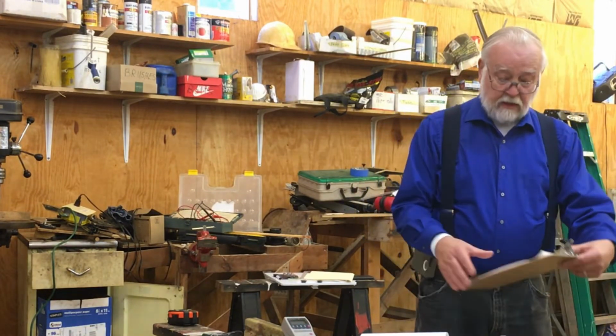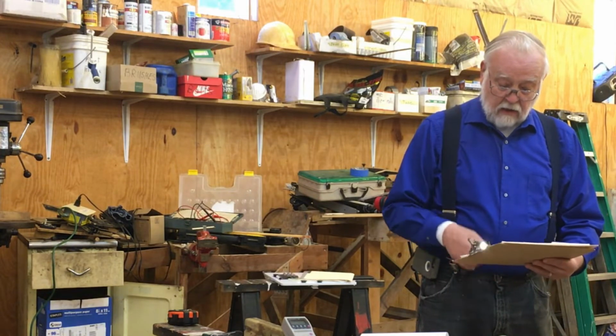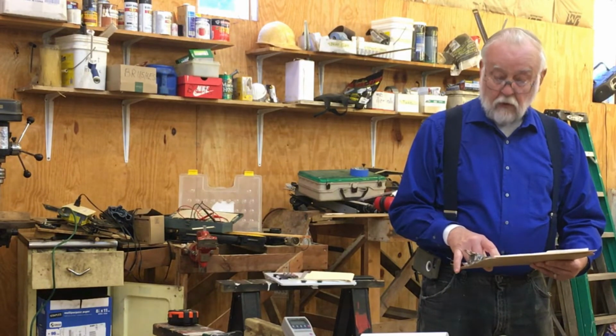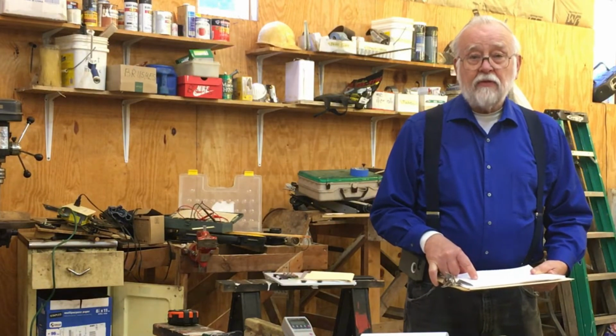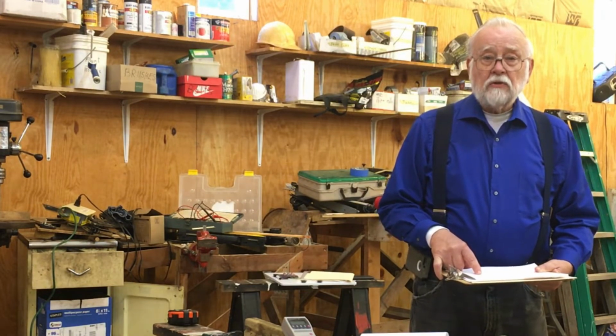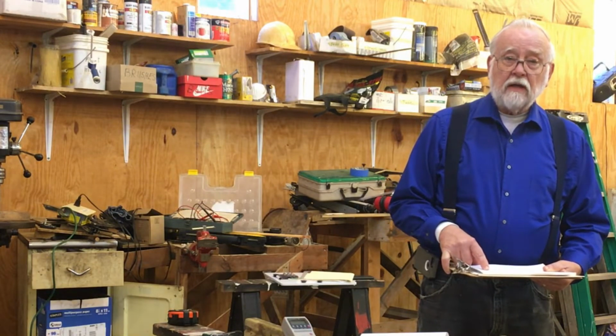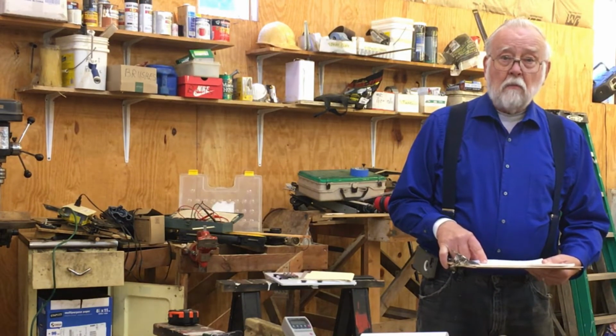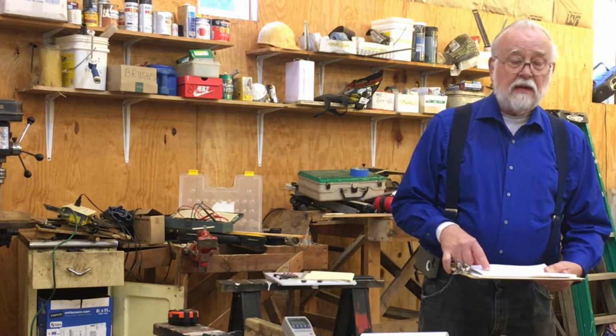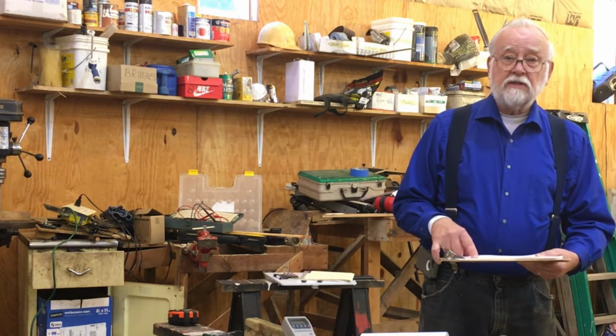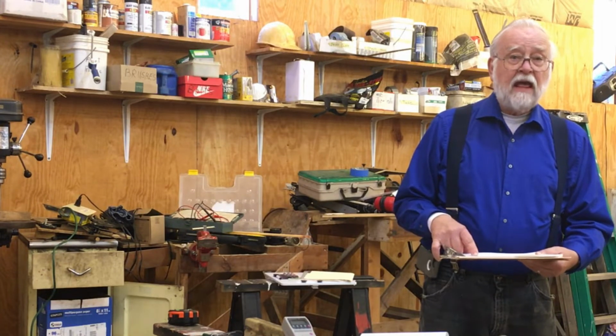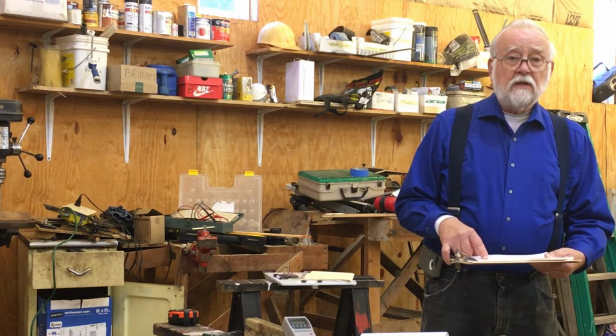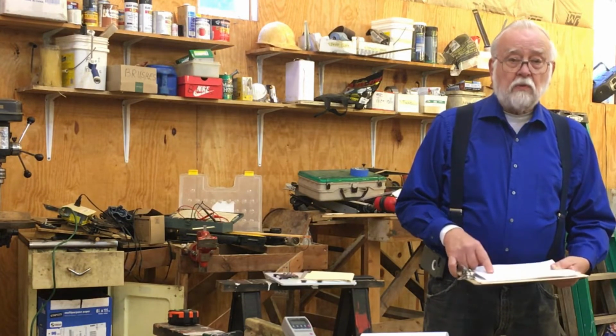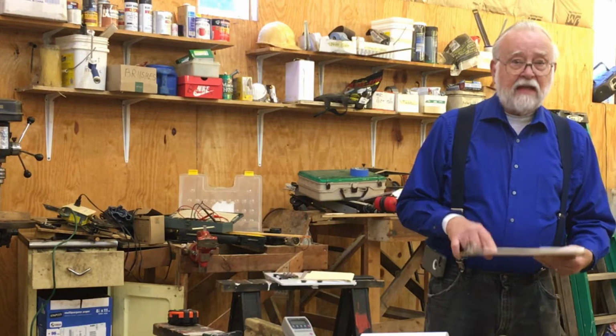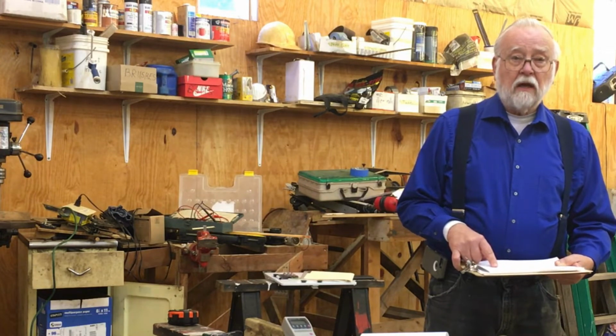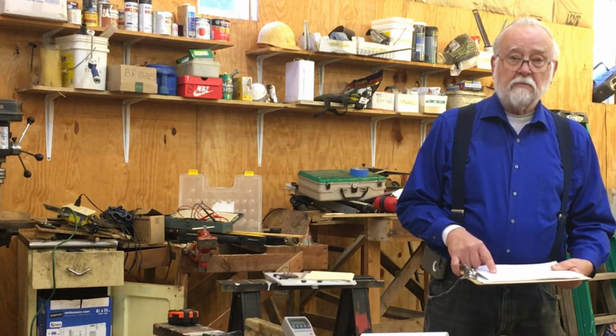It's not good enough for me to take my little chart here, set the resistance for a load that I think is going to be about 3,100 watts, put it on my generator and have it sitting there still running, but it's slowed down. The frequency is maybe 50, 55 hertz. The voltage is down to 105, 110. That's no longer meeting the definition of what's required for an electrical load. And that's where I determine a cutoff for the generator as far as its ability to meet electrical loads.